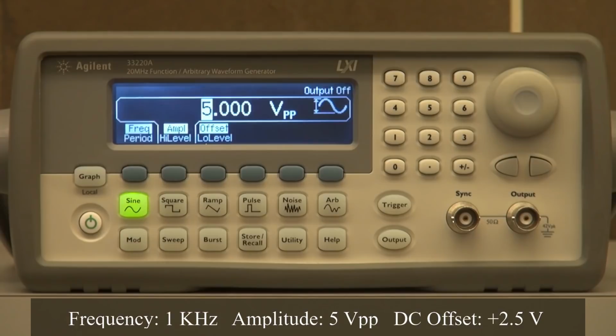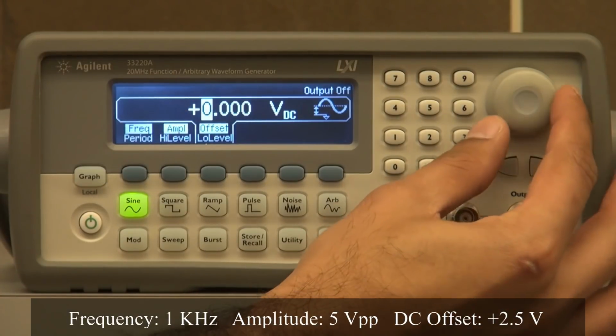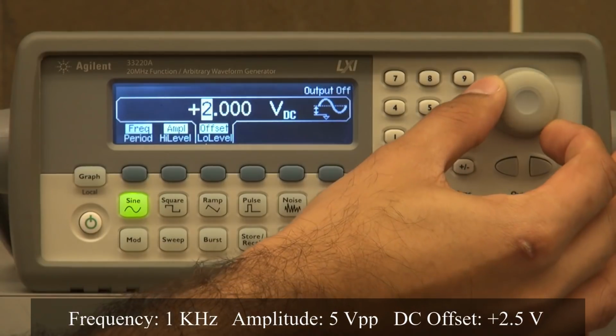Once we are done setting the amplitude, we can now set any DC offset. For demonstration purposes, I will now set a positive 2.5 volt DC offset. I do that by pressing the button labeled Offset, ensuring that Offset is highlighted, and now I can change the value of the DC offset by rotating the knob.